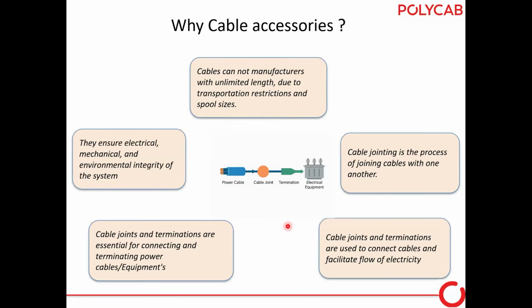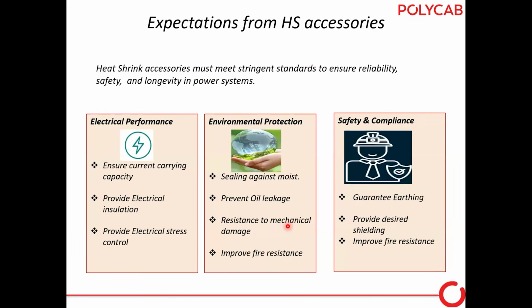Yes, I will show this with the pointer here. Cable joints and terminations are used to connect cables and facilitate the flow of electricity. They are essential for connecting and terminating the cables at the equipment level. Cable joints and terminations ensure the electrical, mechanical, and environmental safety of the system. So these are the functions, the requirements from cable accessories, and that's why cable accessories are required. Whenever we choose any manufacturer for a cable accessory, heat shrink joints or cold shrink joints, any type of joints, what do customers expect from us?